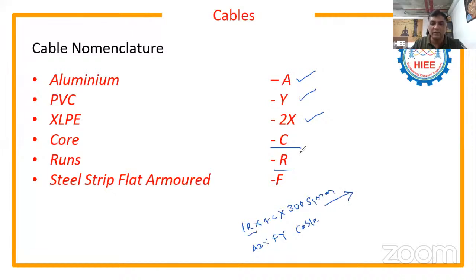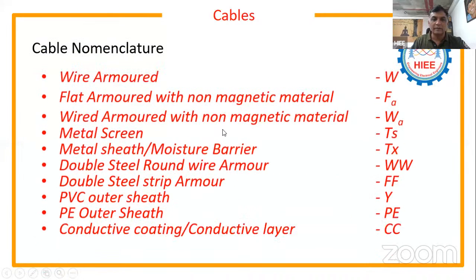R stands for the number of runs, and C stands for core, and F is steel strip flat armored. I have shown you we have two types of armoring: flat armoring and wire armored cables. F stands for flat armored and W stands for wire armoring. Yes, wire armored will be represented with W.